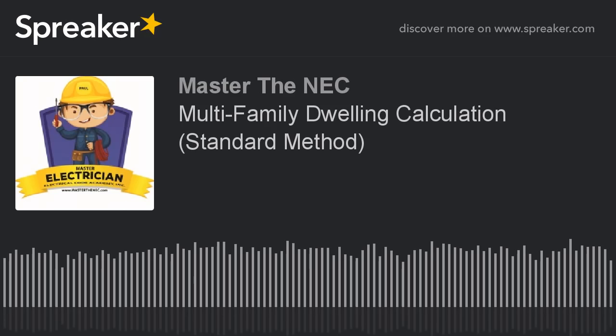All right. Now that's the largest motor within the equation. At this point, this is where sometimes people get confused. They want to add that 25% to all motors. It only says for this calculation that you apply it to one motor. Take the largest motor. So they all have motors, but you take one of the motors and do the extra 25% to it. You don't do that times 18. That's why it's only an additional 294 VA that's added to your service calculation. Don't get confused by that and try to add that additional 25% to all of the motors. You're doing a full calculation here, so you only do one motor.